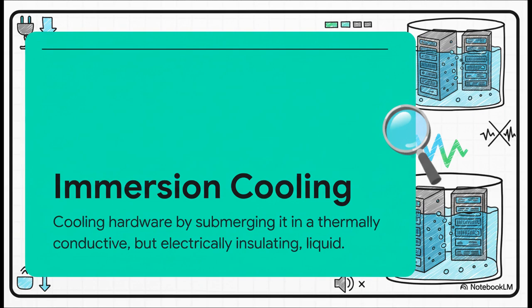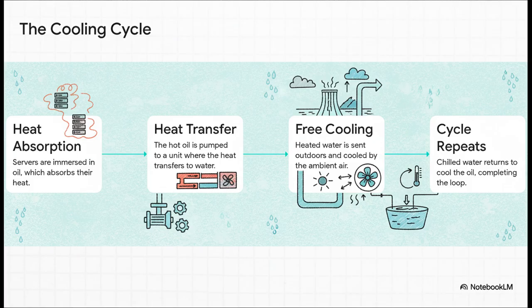It's incredible. So how does the whole system work? Well, it's this really elegant, closed-loop cycle. First, you immerse the servers, and the oil instantly pulls the heat off them. Then, that now hot oil gets pumped to a unit where it transfers its heat over to water. From there, the warm water is piped to an outdoor unit that just uses the outside air to cool it down. They call that free cooling. And finally, that now chilled water cycles right back to cool the oil again. It's just a super efficient way to shuttle heat from inside the chip all the way outside.